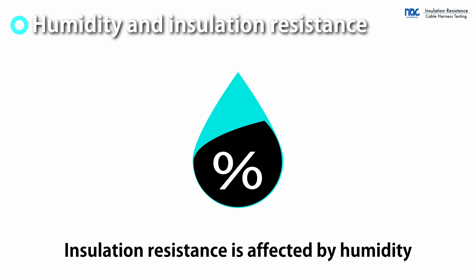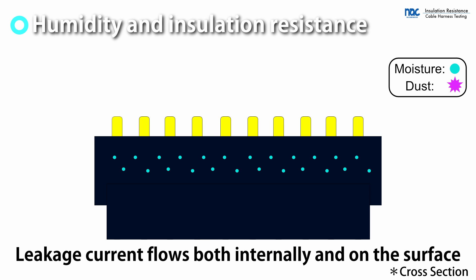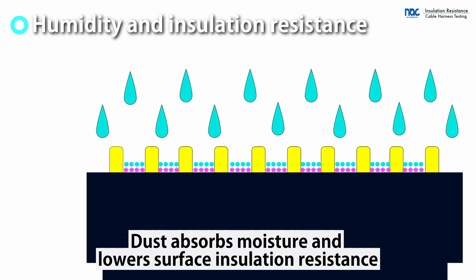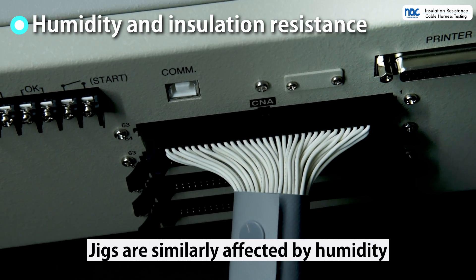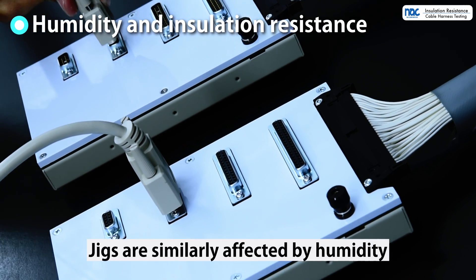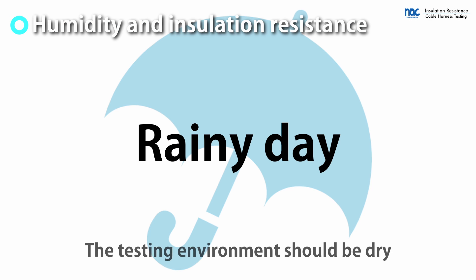Humidity is relevant in insulation resistance. Leakage current flows inside the insulator, but it also flows between conductors through the surface of the insulator. When the surface is dry and clean, the leakage current is low. However, if the surface is humid and dirty, the leakage current tends to flow more. This affects not only test targets, but the jigs as well. It is more likely to occur in seasons of high humidity or when it rains. A dry condition is always preferable for testing.